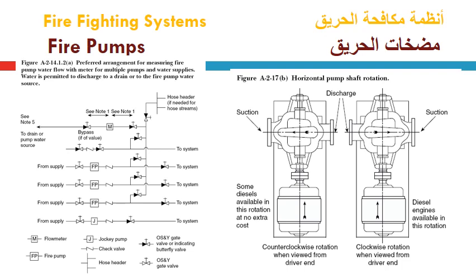This slide presents the preferred arrangement for measuring fire pump water flow with a meter for multiple pumps and water supplies. Water is permitted to discharge to the drain or to the fire pump water source after going through the meter. All these suction sides from the suction tank supply water to the main fire pumps, even two or three electrical driven or diesel driven, and the jockey pump. Each pump has its isolation valve of OS and Y gate valve located here, and then after the pumps we must use a non-return valve or check valve, which is located here, and then each pump also has its isolation valve of gate valve OS and Y.